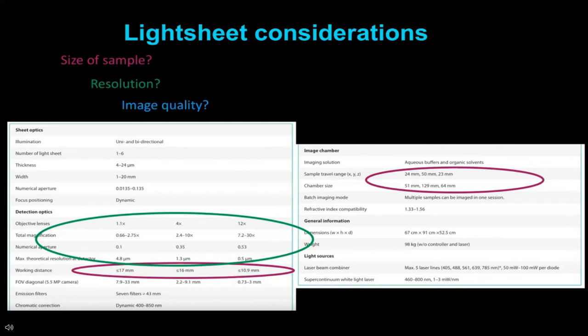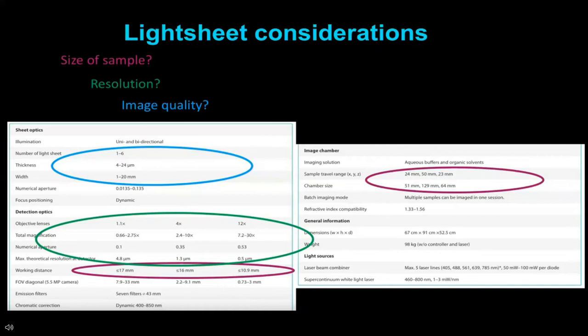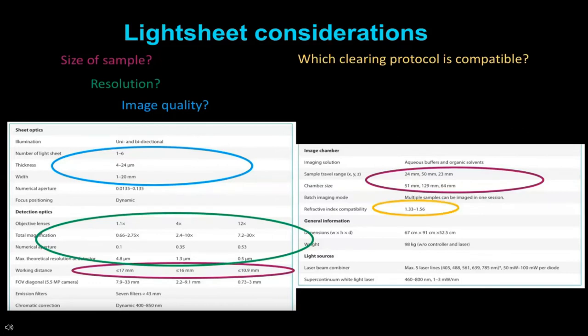Image quality: you want to look at how many light sheets you can get—six would be three from each side. Then your light sheet thickness; you should aim for around five microns. Also, is your clearing protocol compatible? You want to look at compatibility with refractive indices, and you will often find you can use either a water-based protocol or a DBE or ethyl cinnamate based protocol.